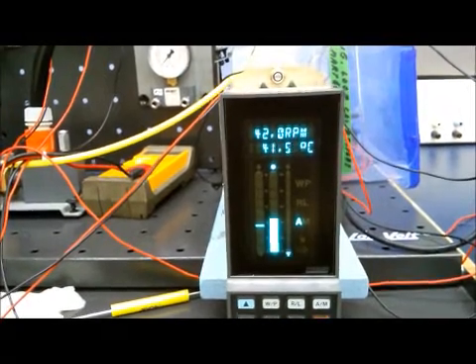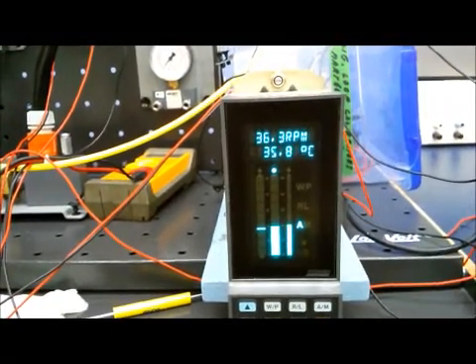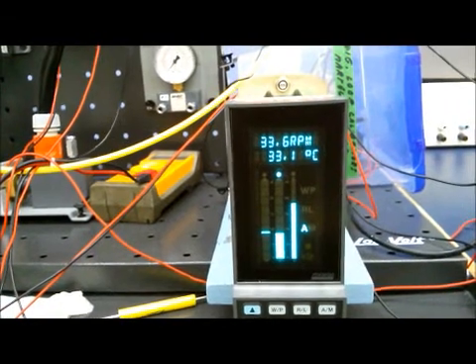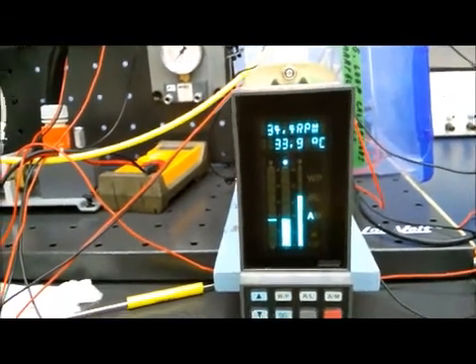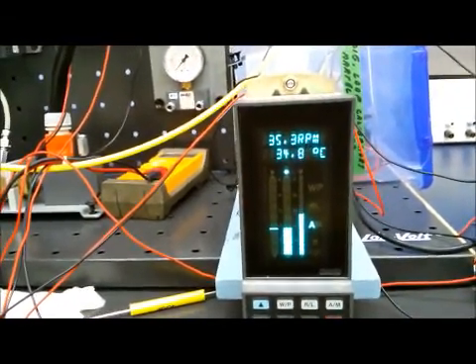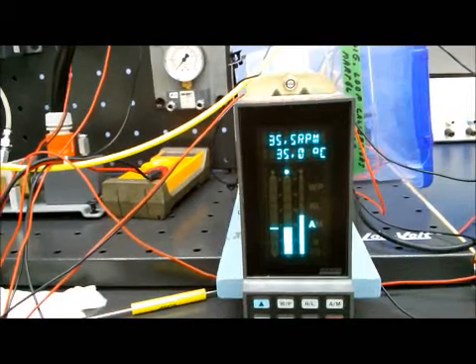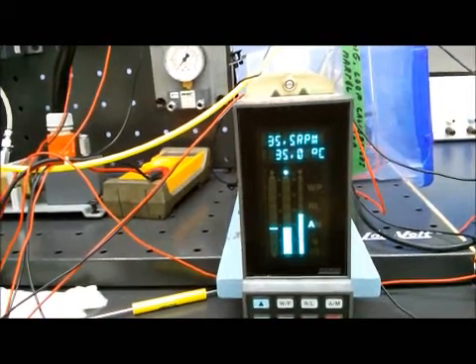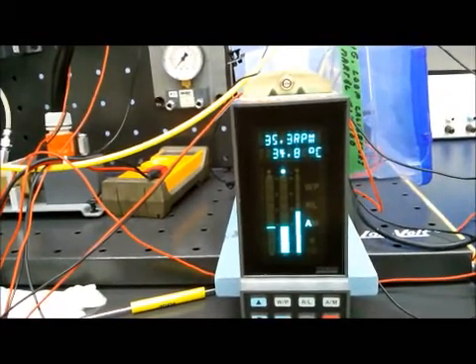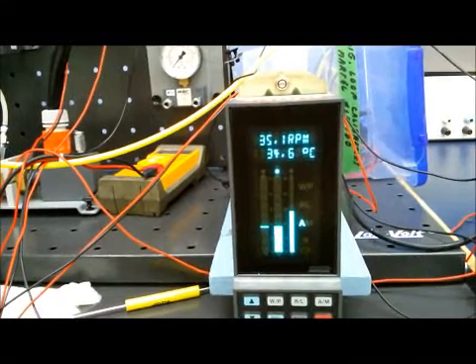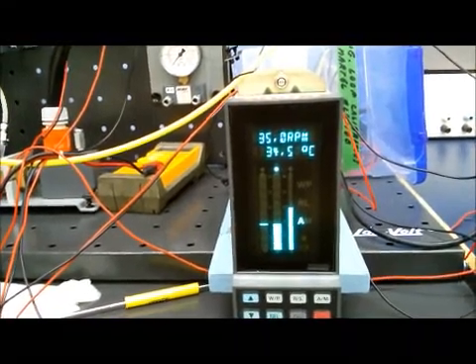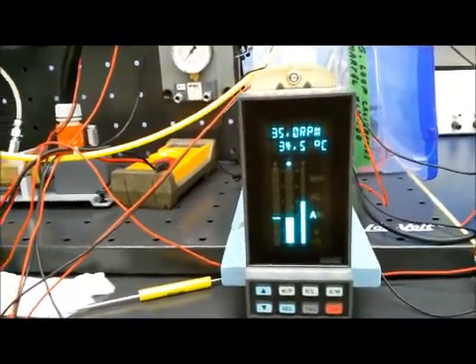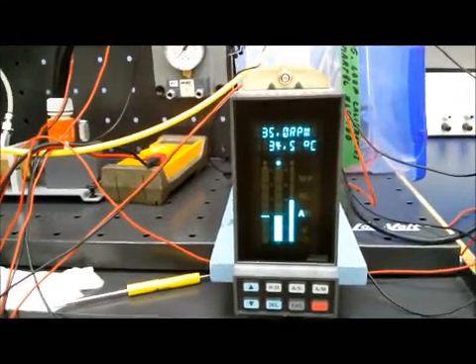So, proportional band of 10%, that's just a slight overshoot, which is okay. Seems to be pretty darn good with proportional only.